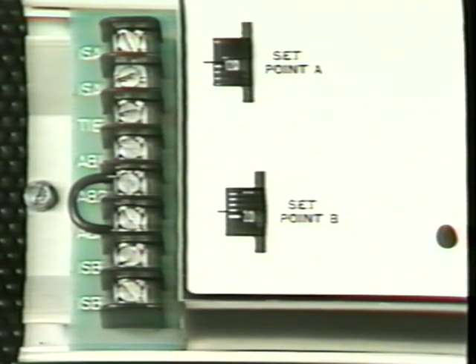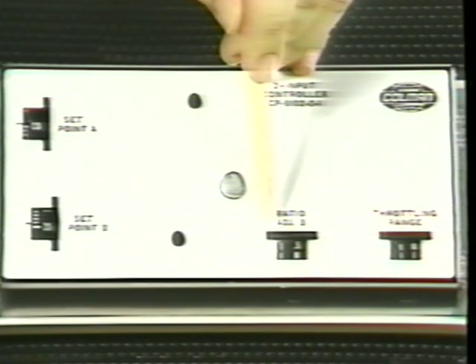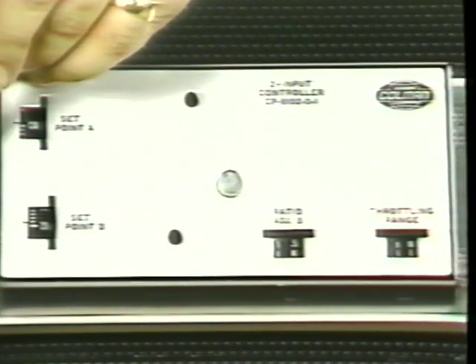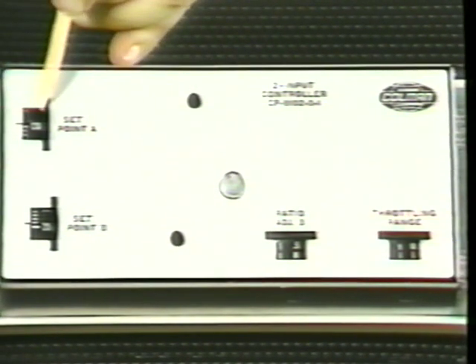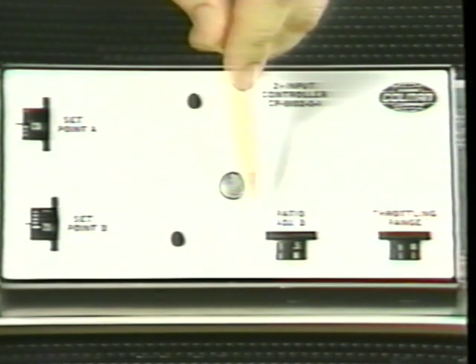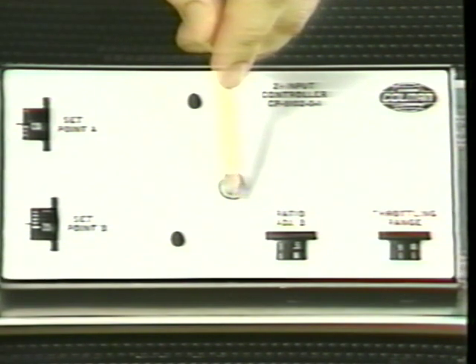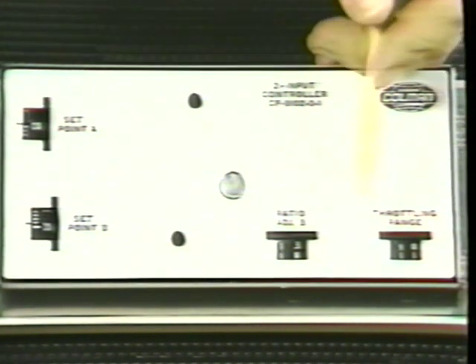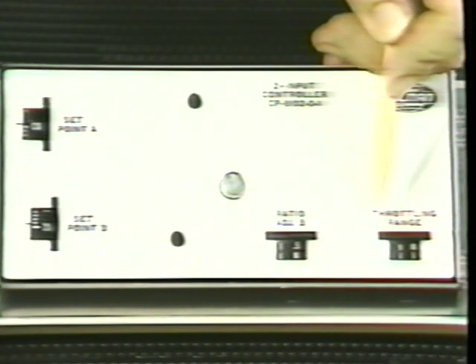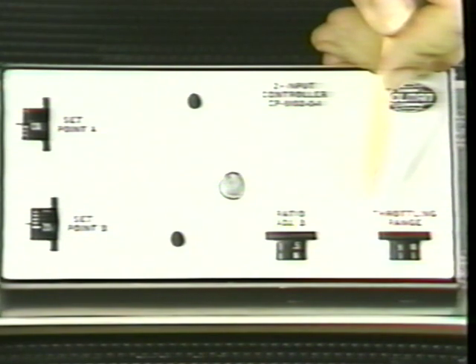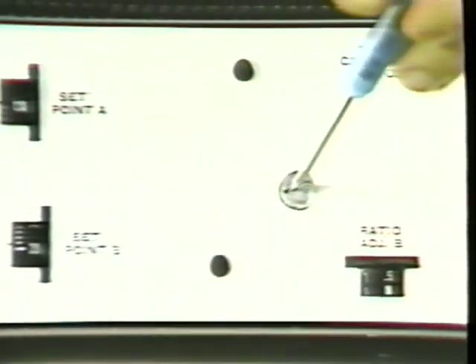Another example, with the setting on the ratio pot of 25, it would be read as 25 to 1 B to A, and now it would take a 25 degree change at sensor B to give the same 1 degree reset of set point A. The ratio adjustment pot functions only when bridge B is operational. Finally, throttling range. This is a variably adjustable pot allowing a 2 to 10 degree Fahrenheit throttling range. Additional adjustments are beneath the cover.